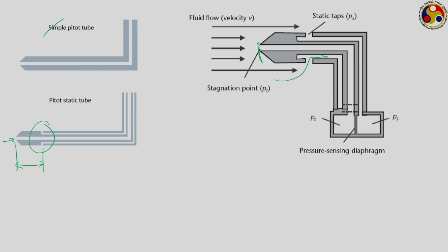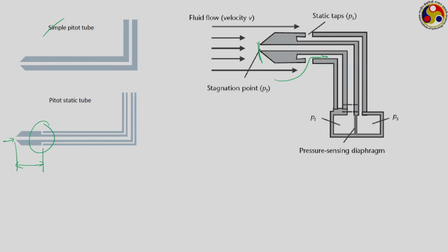So, the pitot-static tube is a very standard, quite accurate, and also a very simple and cheap method to measure fluid velocities and correspondingly the flow rate of the fluid. However, one important thing which definitely affects its accuracy is the position of these holes, and for that the position of the nose and the stem is very important.